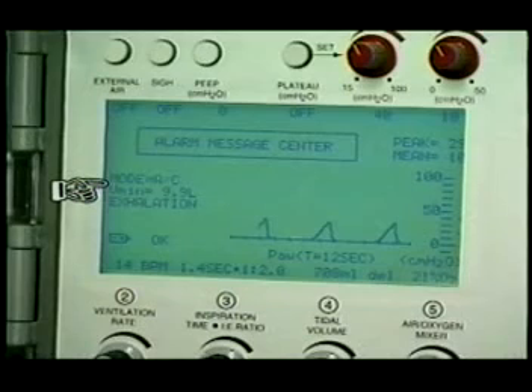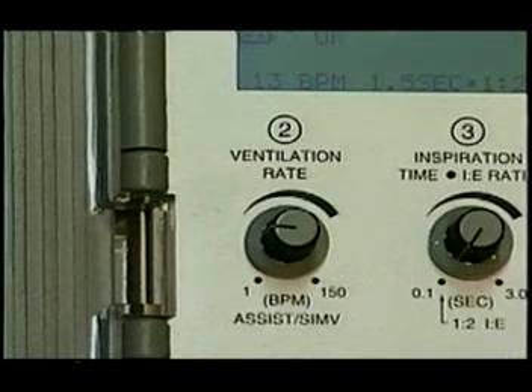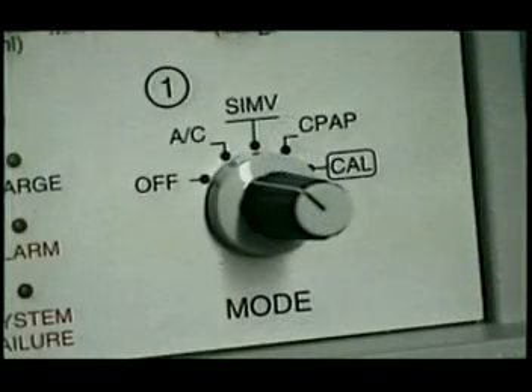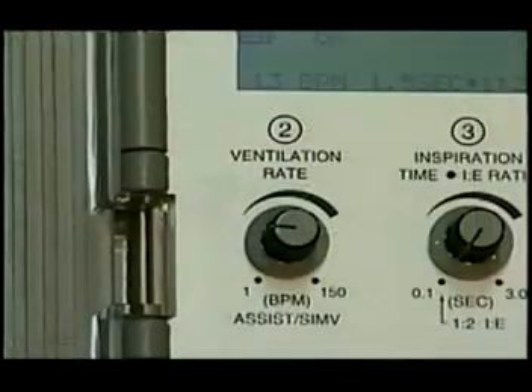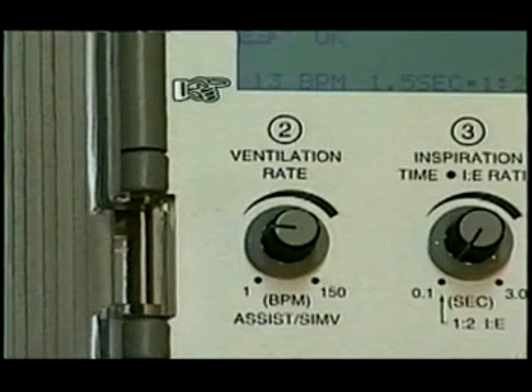The mode indicator displays the current setting of the mode selector switch. The VMIN indicator displays minute volume in liters in the AC mode. The ventilation rate control is the control number 2. It sets the mechanical ventilation rate for AC or SIMV. Its range is 1 to 150 breaths per minute, or BPM, based on the control position, and its value is displayed in the LCD above this control.